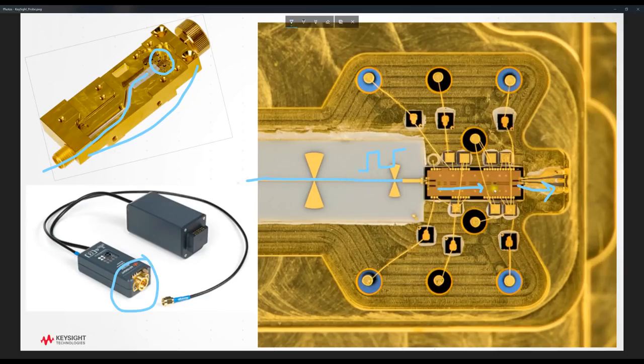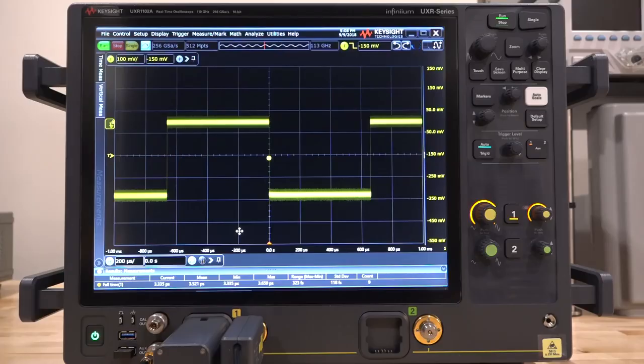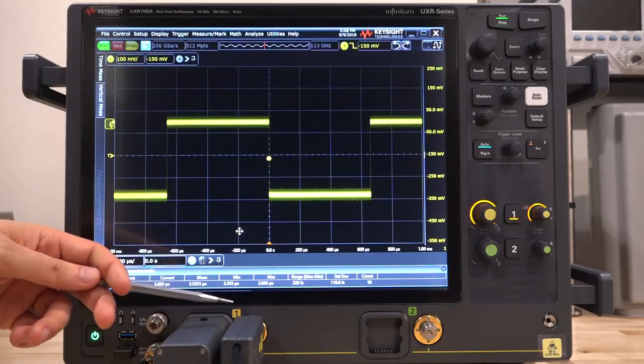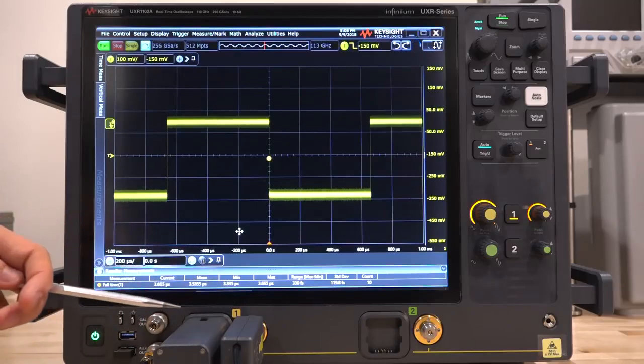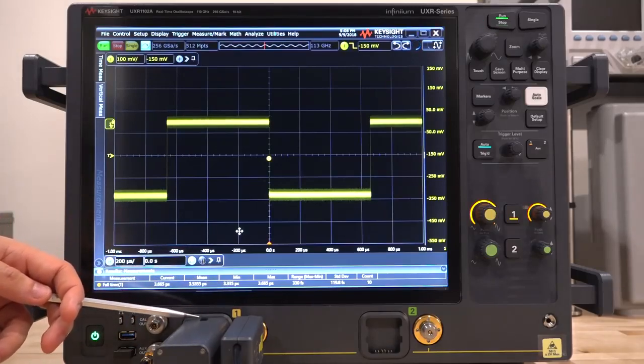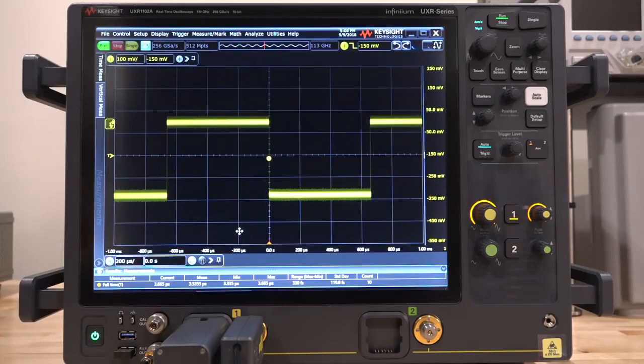So having said that, this is what's inside this, all designed by Keysight again, from scratch, just for the purposes of being able to do this NIST calibration directly on this oscilloscope itself, which is really quite impressive. So now that we know how it works internally, we can go ahead and connect it to the scope and see how it behaves. And here I have the calibrator directly connected to channel 1 of the instrument, and the interface to the front of the scope, the probe interface, is also connected, and the auxiliary output of the scope, which generates the square wave, directly goes to the calibrator.